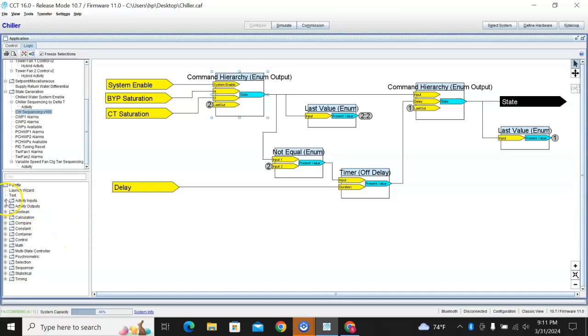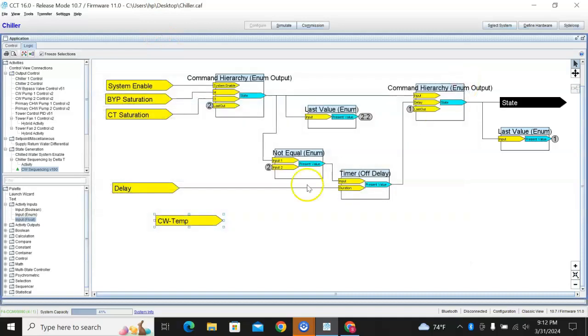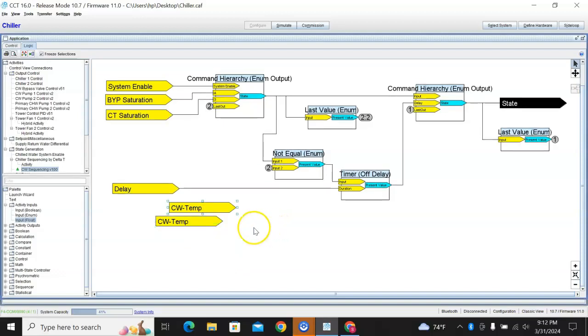So what I suggest doing is you can come in this block or you can do it in a different block, it doesn't matter. Adding an input float, call this condenser water temp. Duplicate it, add in another float, however you want to do it. Call this one set point, condenser water temp set point.